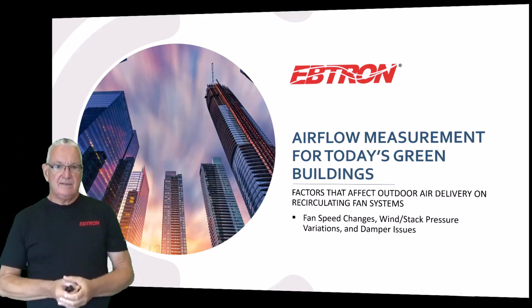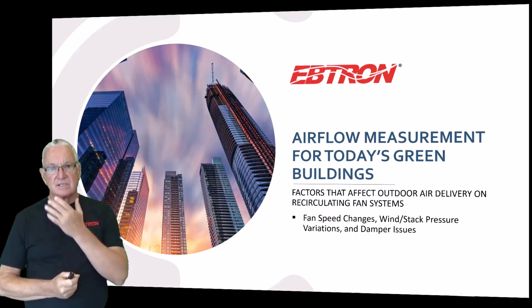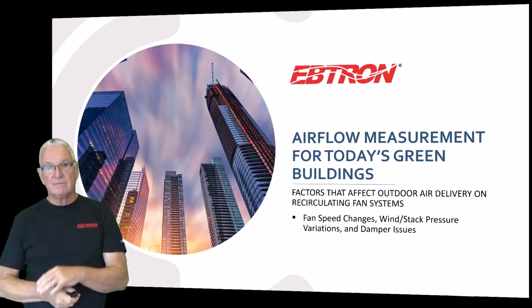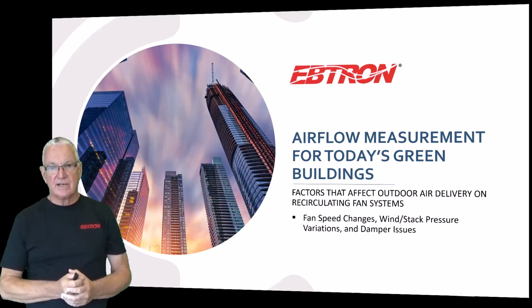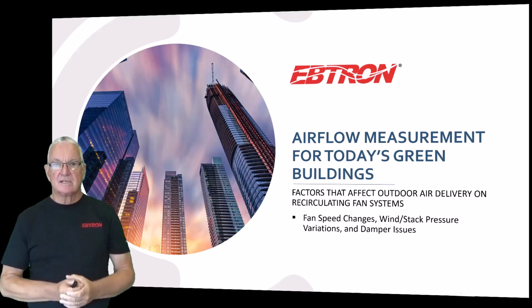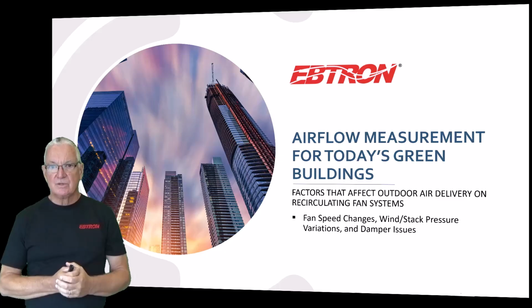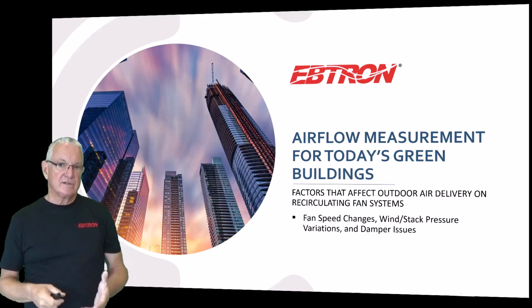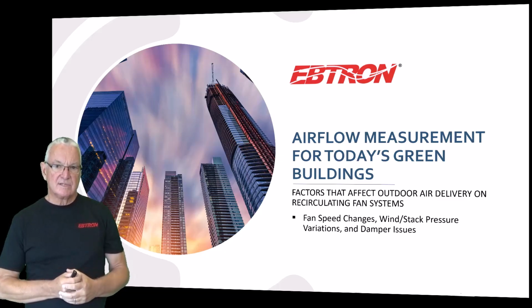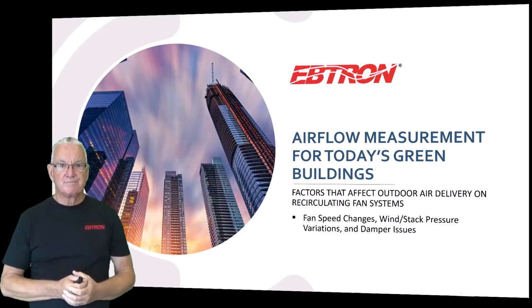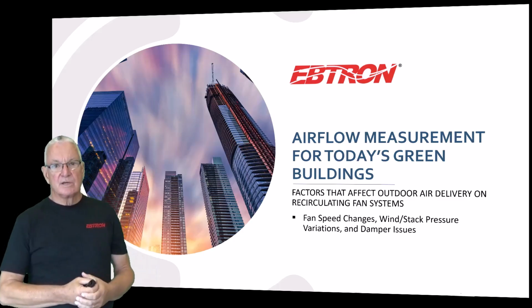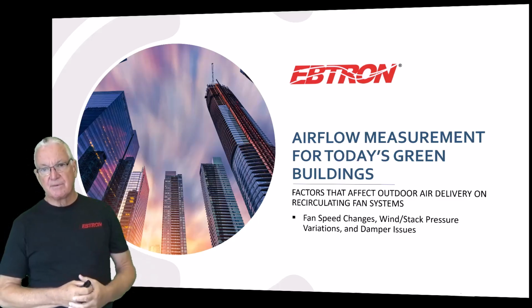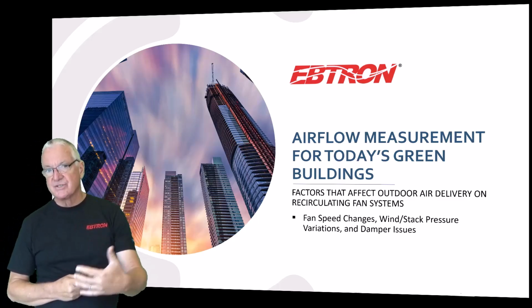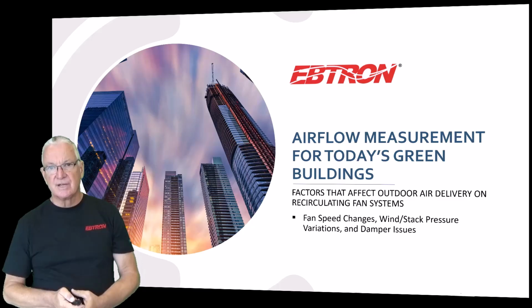Okay, in our deeper dive, we're going to talk about factors that affect outdoor air delivery. In this case, we're going to talk about recirculating fan systems, although quite honestly, you can apply some of this to DOAS systems. It's just recirculating air systems have even more problems, really. So we're going to look at fan speed changes, wind and stack pressure, and damper issues, okay?